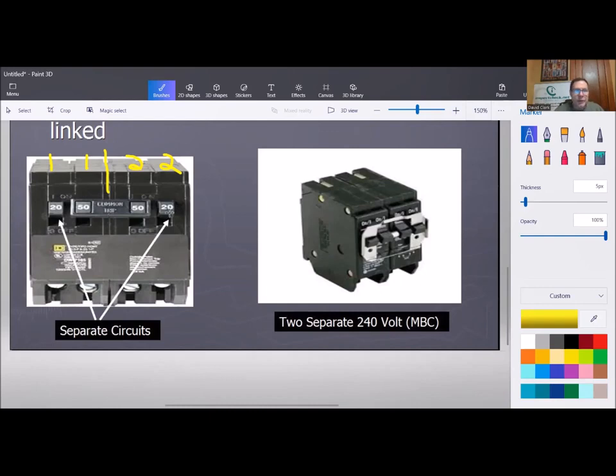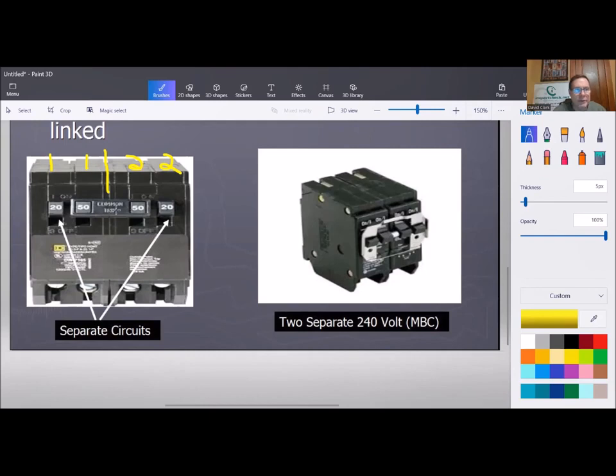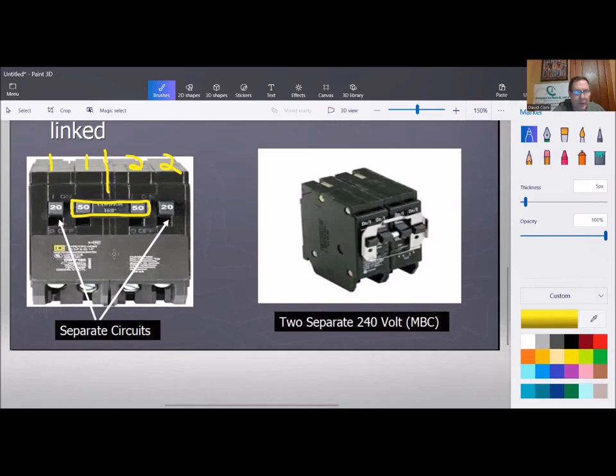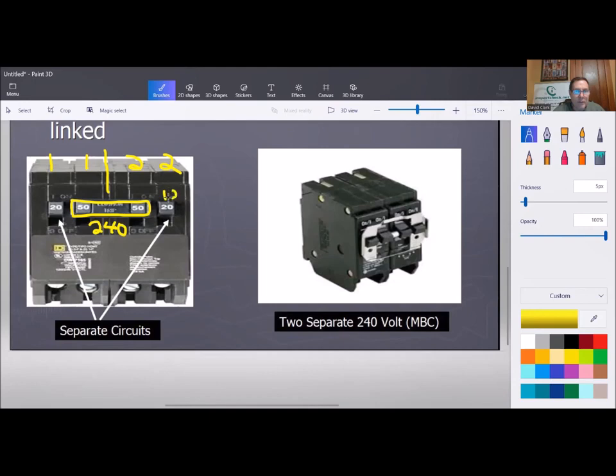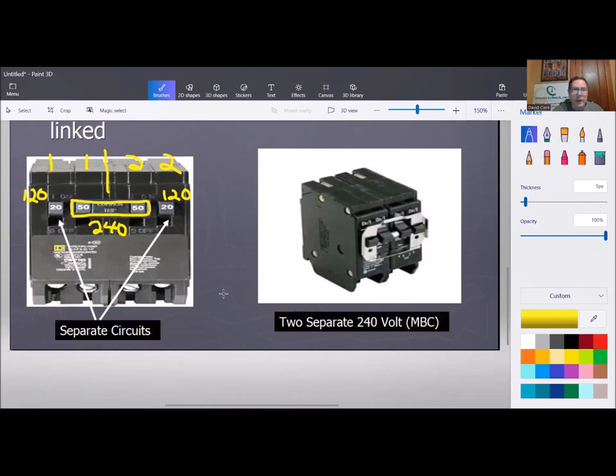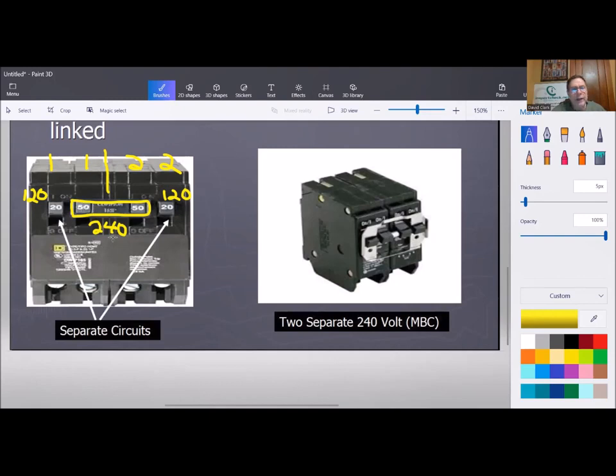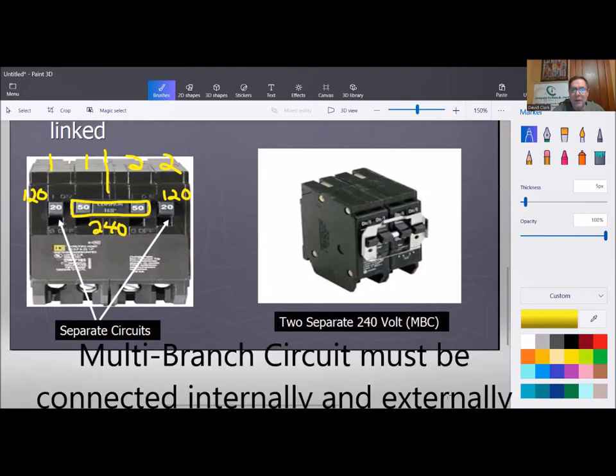These are going to be separate circuits and they're independent trips. So this would trip independent of these. Even though some common trips might trip all of them, it depends on the manufacturer. But in this case, these are the common trip just this 50 amp. And so that's going to be for a 240 volt circuit, a dryer or stove or something. Probably not a hot water tank. And these are independent. So this will be 240. And these are both going to be 120. And that common trip is what we like because we could only use a common trip for a multi-branch. So if this were a 15 or 20, I mean, you're not going to have a 50 for a multi-branch circuit in a residence. I've never seen that. But that would be a 15 or a 20. And then with the common trip noted there, we could use that for a multi-branch circuit because a multi-branch circuit should be connected mechanically.